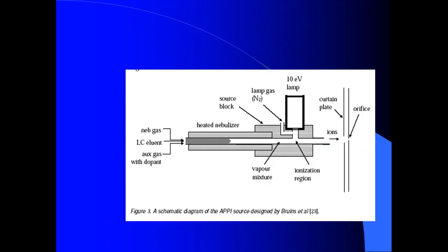Atmospheric pressure photoionization basically ionizes the sample analyte by irradiation of short wavelength vacuum ultraviolet light. The interface design of APPI is very similar to APCI, the only difference being the swap of the high voltage corona discharge needle for the vacuum ultraviolet lamp. Similarly, the nebulizer and the heater are used to create droplets and to vaporize the sample. The remaining process is almost the same.